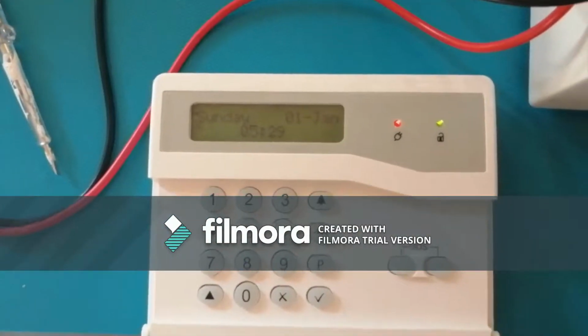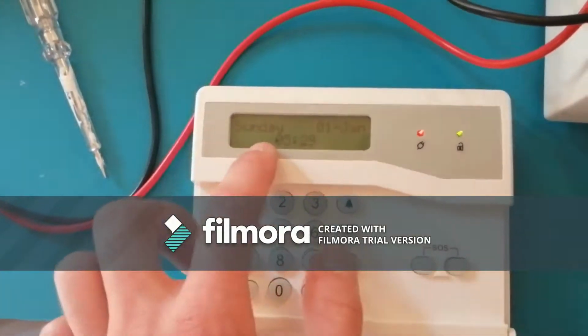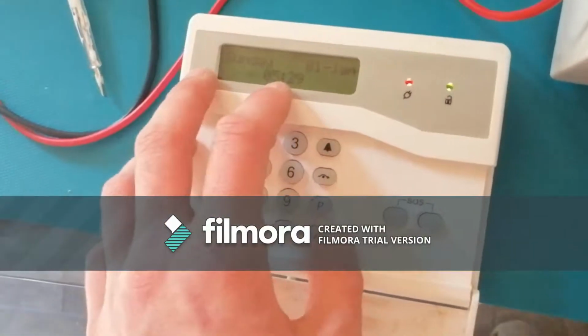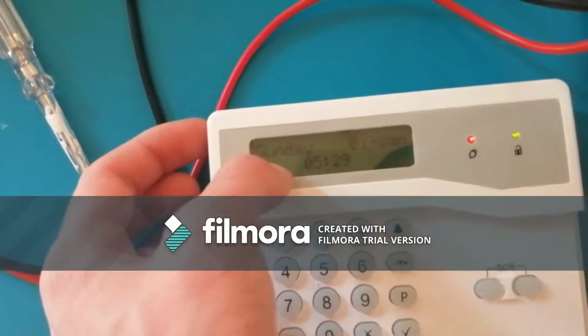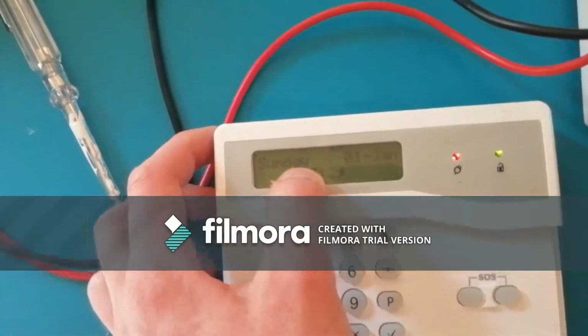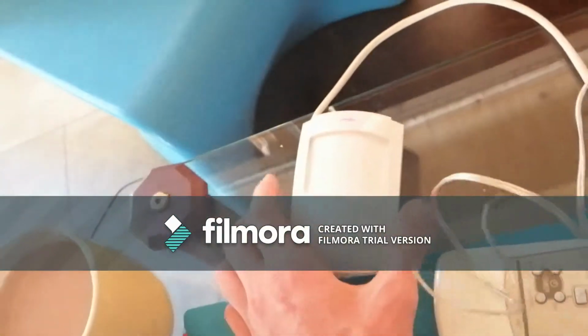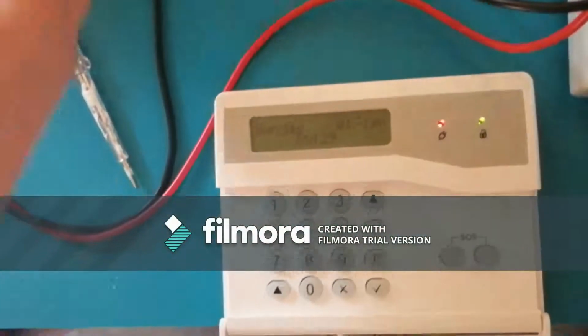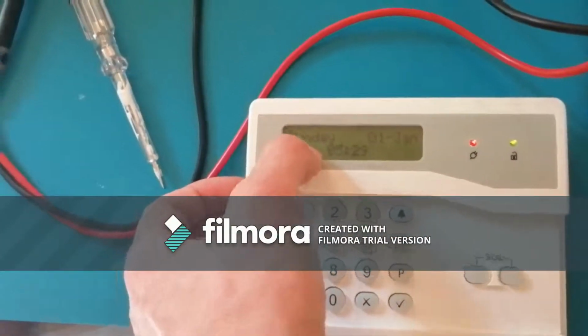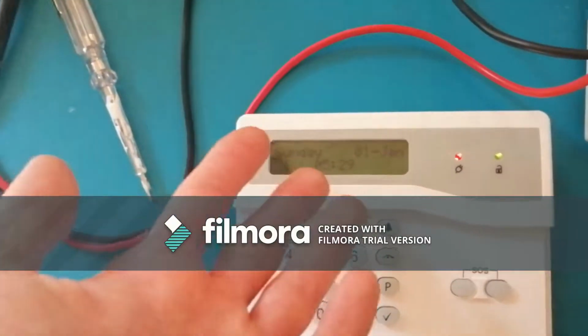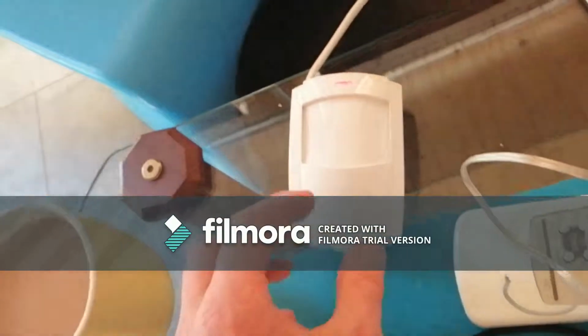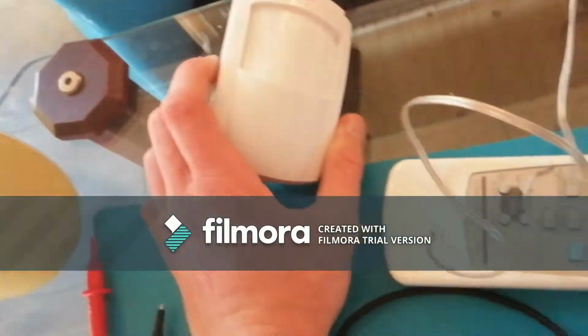So if it's an LCD keypad like this, it will have a zone descriptor. Now if it's programmed correctly, the zone descriptor will identify to where the cause of the problem is. Okay, so if it says setting fault living room, for example, then you know that the cause of the fault is the sensor in the living room.